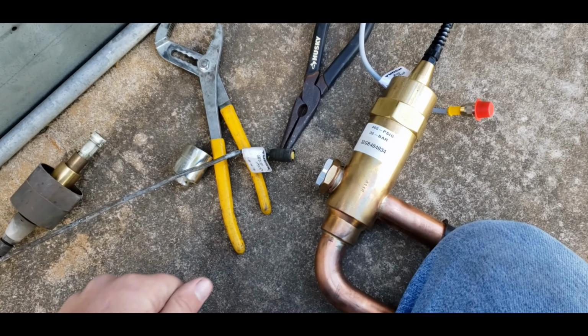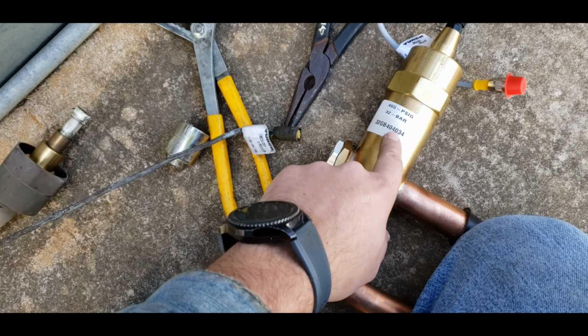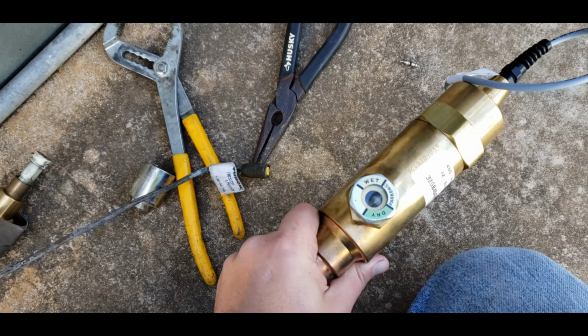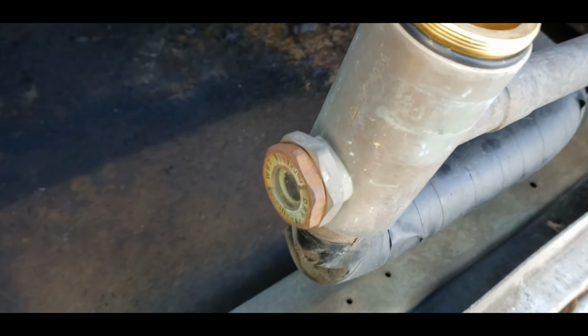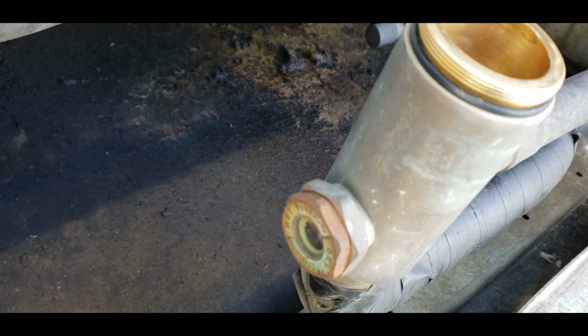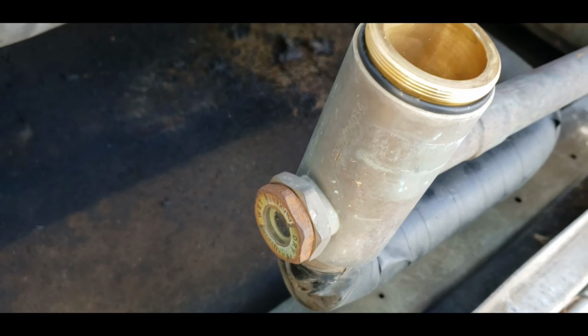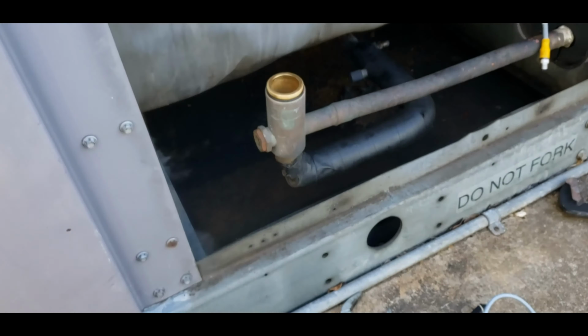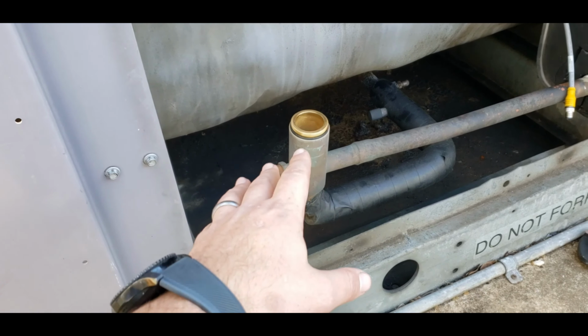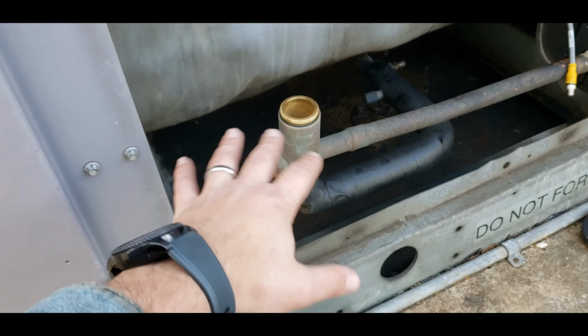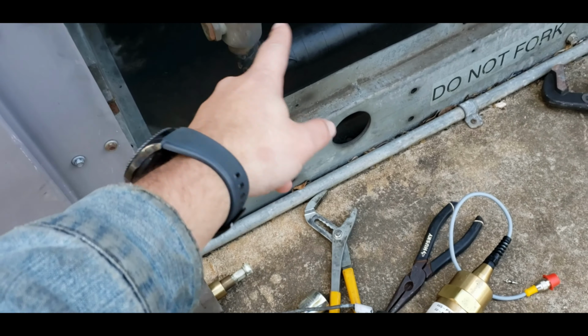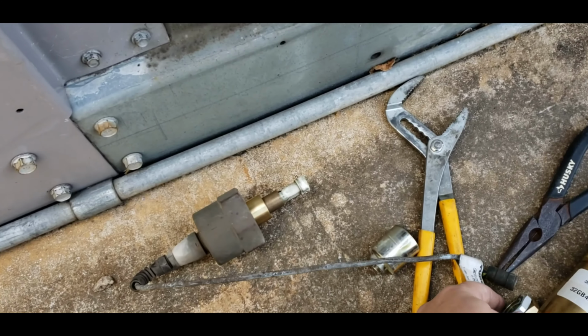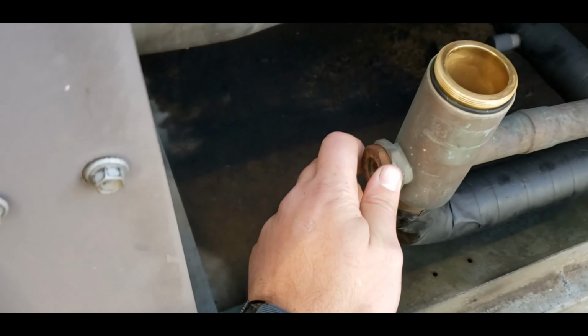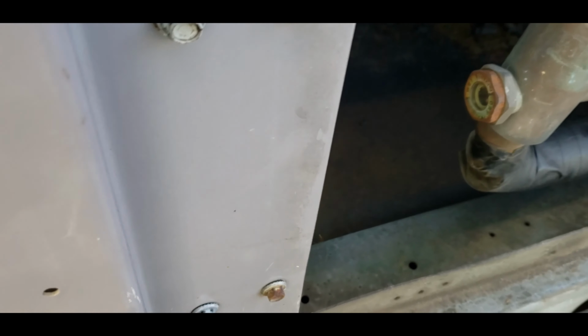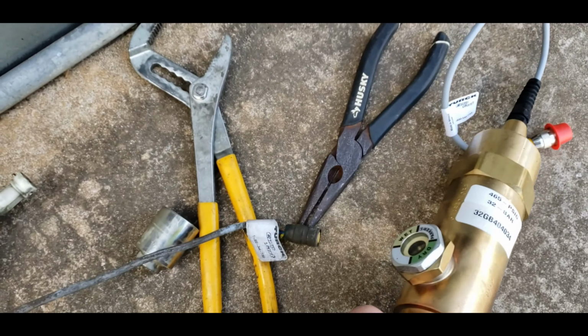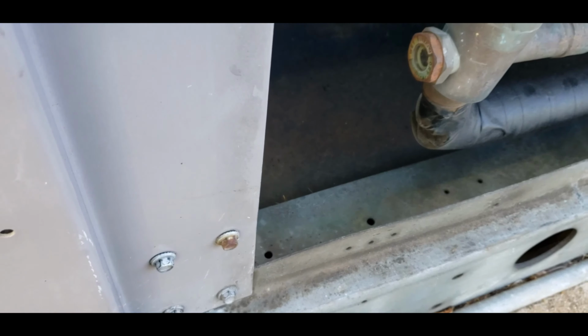One of the things I've verified here is this is the part number. It's also stamped on the front of the valve, and I've confirmed that the valve body part number is identical. That's exactly what I want to see, to make sure these valves are an identical match so that when I switch the heads out, they're good to go. I'm also going to switch out the sight glass here to get a fresh one in there with a new indicator, which should be good for it too.